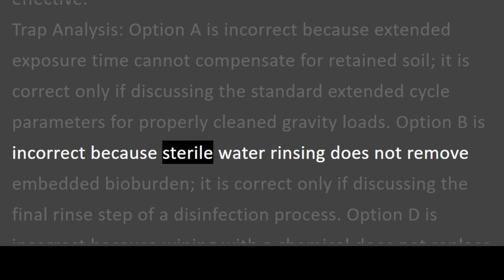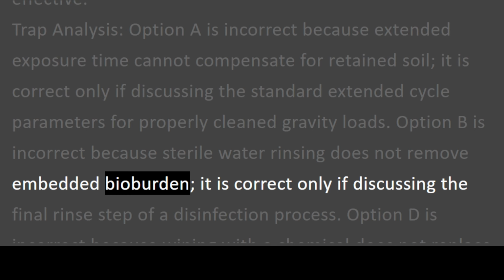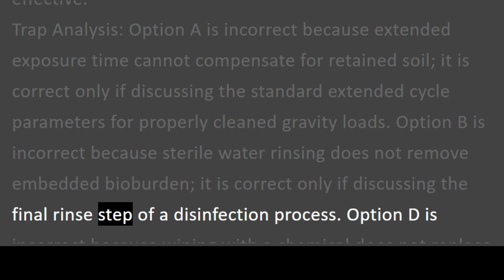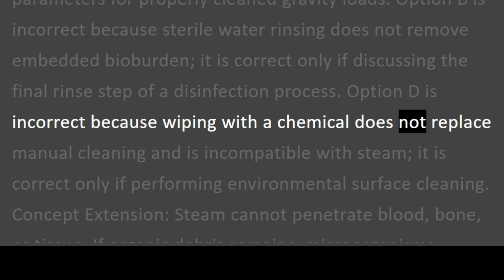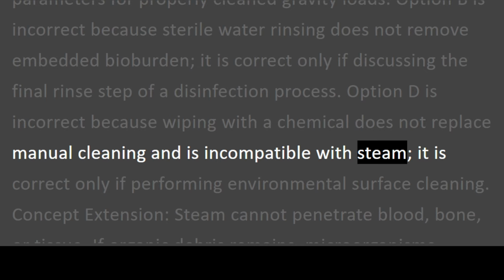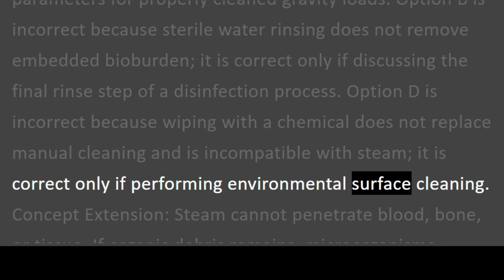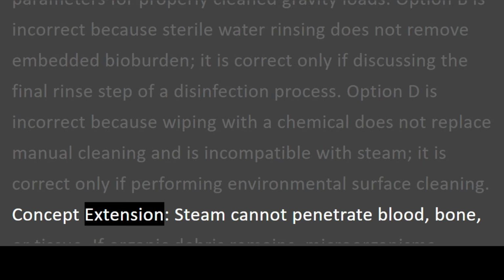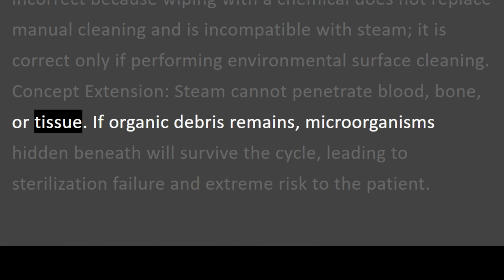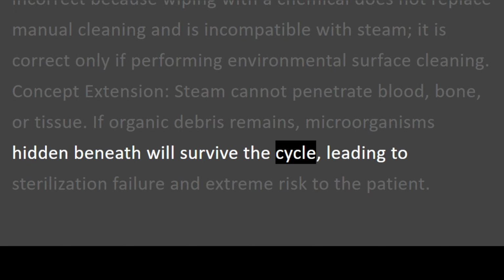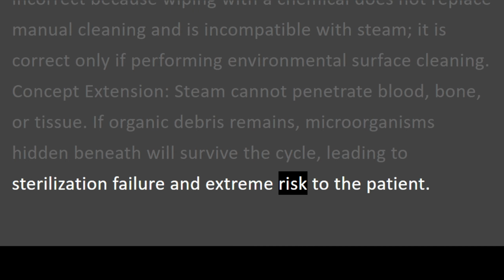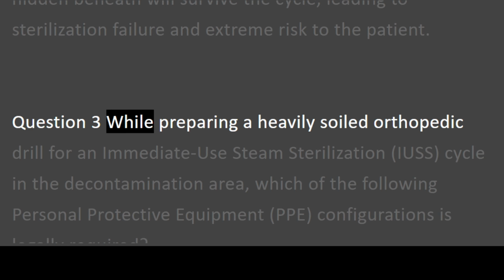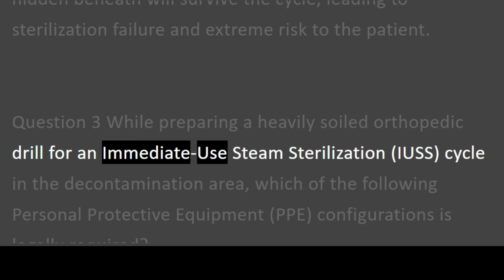Option B is incorrect because sterile water rinsing does not remove embedded bioburden. It is correct only if discussing the final rinse step of a disinfection process. Option D is incorrect because wiping with a chemical does not replace manual cleaning and is incompatible with steam. It is correct only if performing environmental surface cleaning. Concept extension. Steam cannot penetrate blood, bone, or tissue. If organic debris remains, microorganisms hidden beneath will survive the cycle, leading to sterilization failure and extreme risk to the patient.